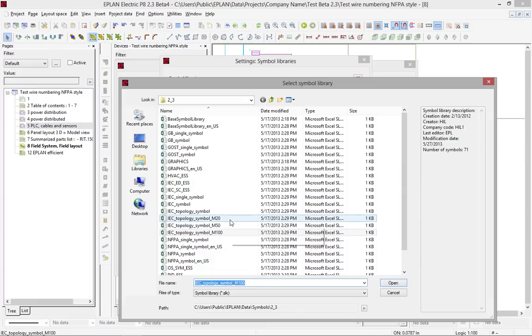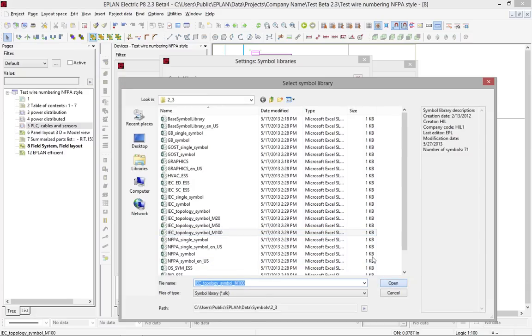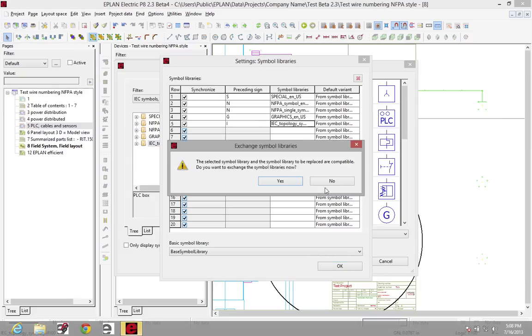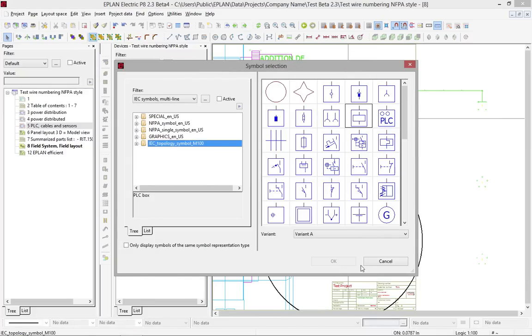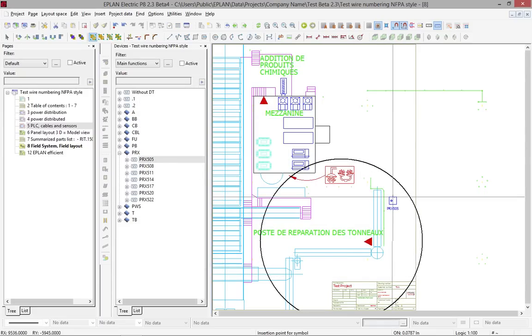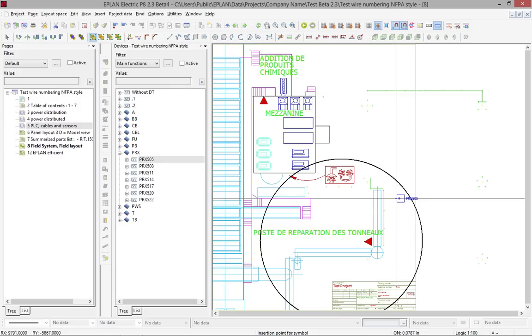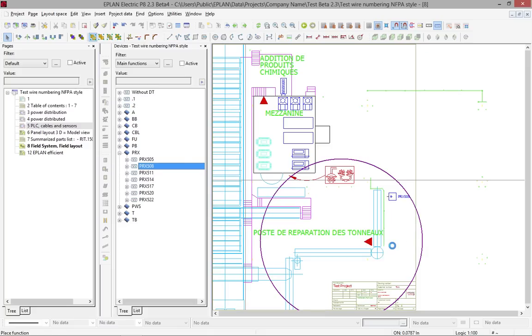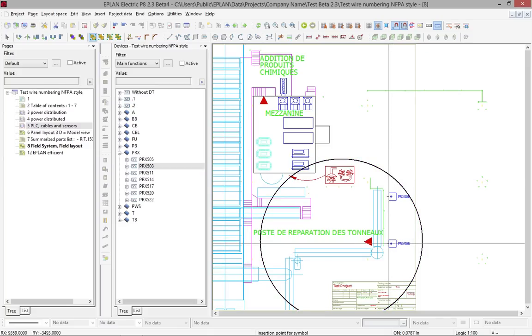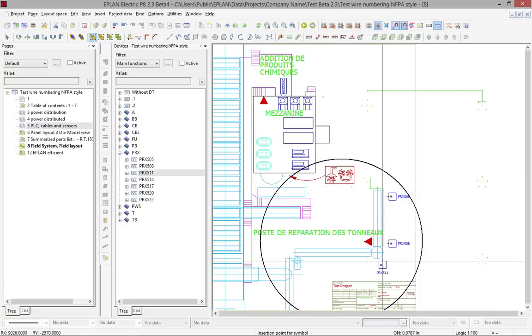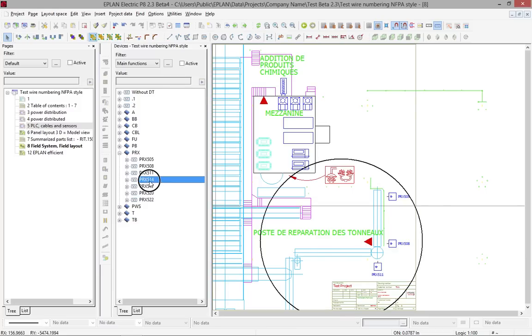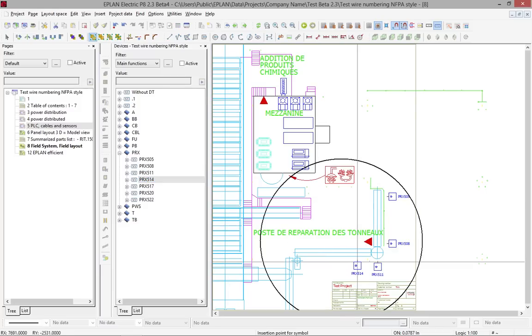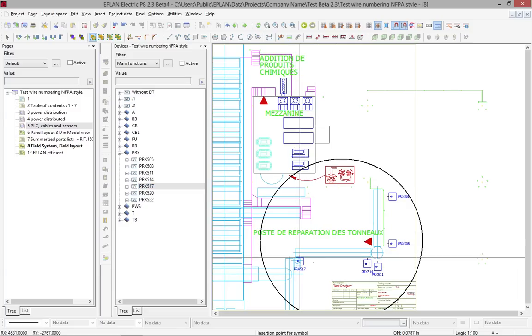Depending on the scale of your overview, if you have a scale of 1 to 20, I recommend the M20. A scale of 1 to 50, I recommend the M50. And the scale of M100 will actually be perfect for a 1 to 100 scale, as I have it here on that particular drawing. So now I can actually drag and drop. You have the representation to represent the proximity switch. You actually go in this 1 to 1 drawing that was provided by the mechanical guys, and you position the different proximity switches in whatever areas you actually need them.